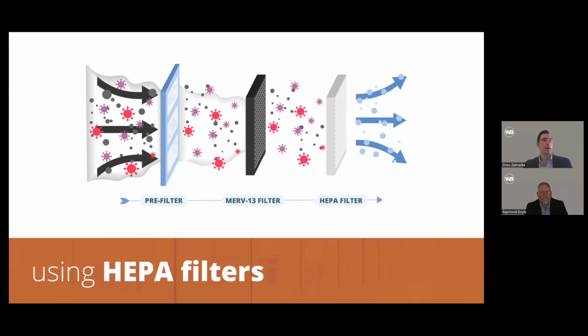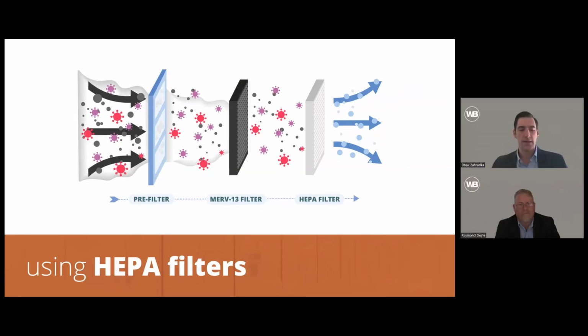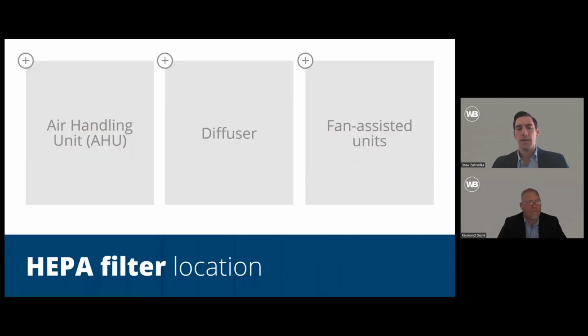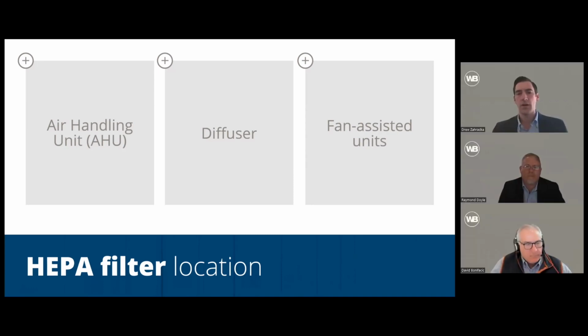So first and foremost, a clean room is quantified by the amount of contaminants at certain particle sizes. Ray mentioned down to the micron, and in order to filter out particles of that small a size, we need to use HEPA filters. HEPA filters have a 99.97% efficiency down to 0.3 microns. Because the HEPA filters can filter out such small particles, we need to take out the bigger particles ahead of that. So you'll use a pre-filter, an intermediate filter, which is like a MERV 13 or MERV 14 filter, and then your final filter, which will be your HEPA filter. The HEPA filter can be located either at the air handling unit, in the diffuser, or in the room via a fan-assisted HEPA filter or fan filter units.